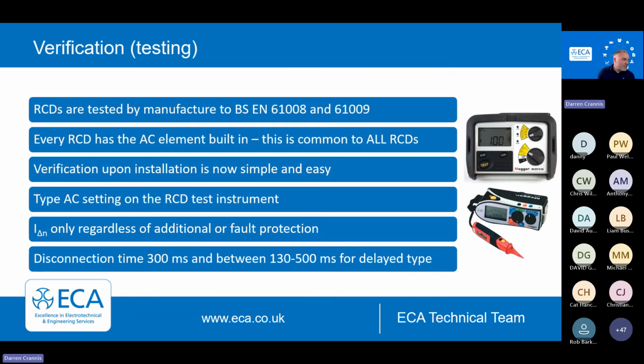Testing, nice and simple with Amendment 2. It sort of took away that times 5 value. So RCDs are deemed effective if they disconnect in less than 300 milliseconds at times 1. You can choose if that's at 0 or 180. The times 5 test isn't there anymore. You may wish to do it, but it's not essential.